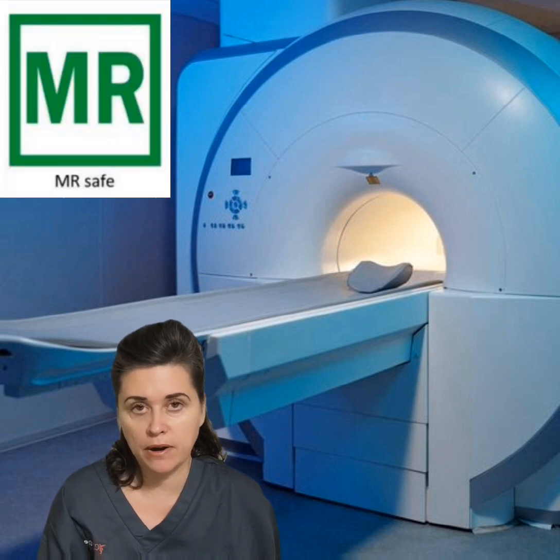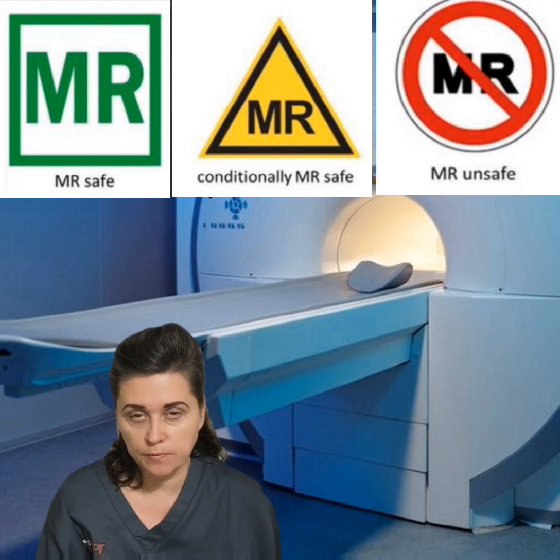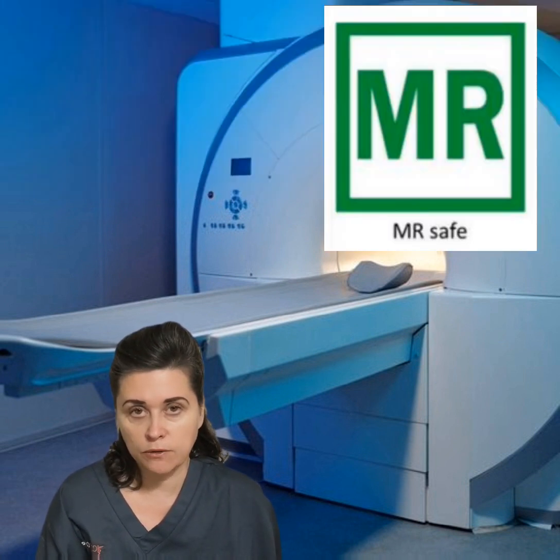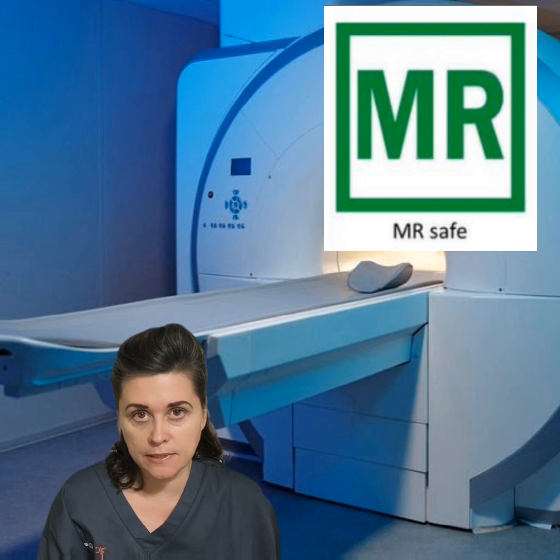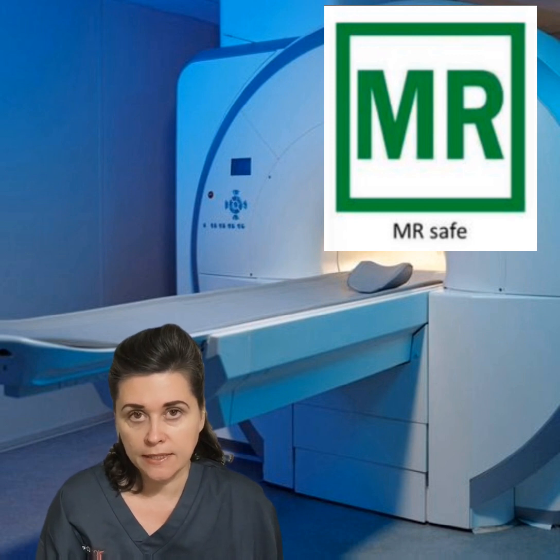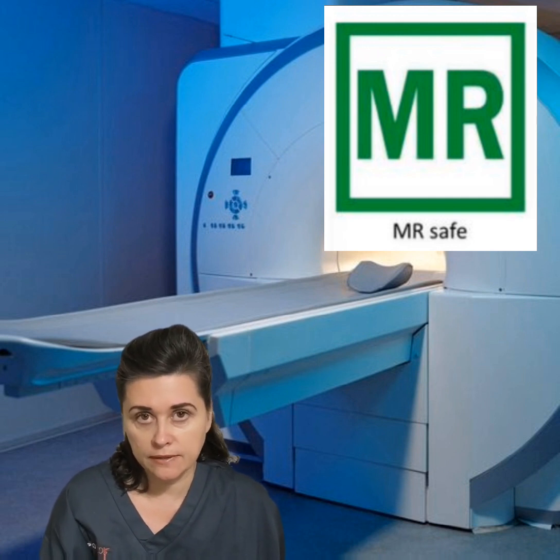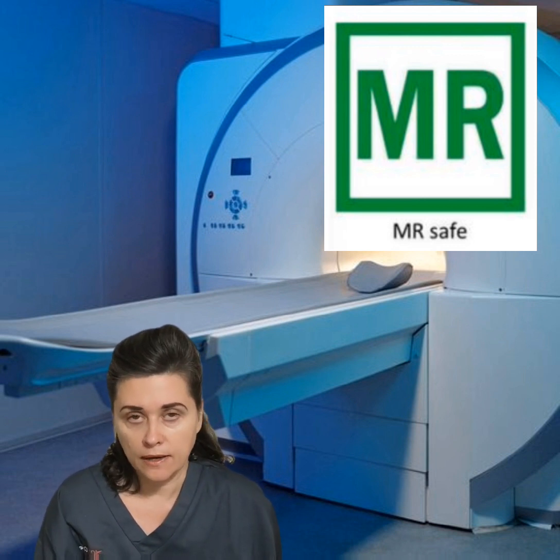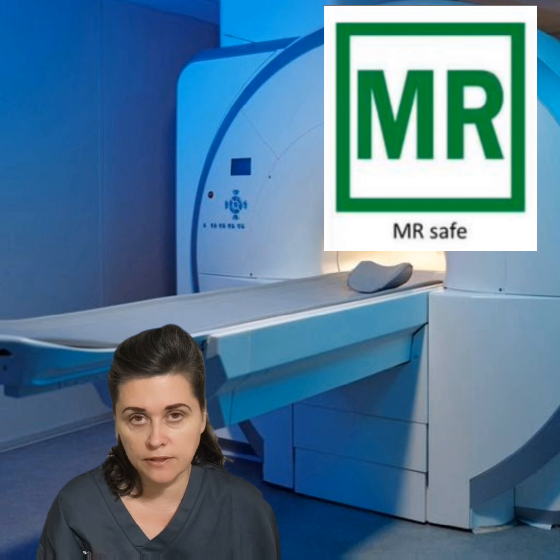In the MRI environment, it is crucial to know the difference between MR safe, MR conditional, and MR unsafe items. MR safe items are usually non-metallic and possess no or minimal heating potential. We have to remember that we have two major forces to watch out for in the MRI scan room. It is B0, which is the static magnetic field, and RF, radio frequencies, that tend to heat up things and objects. So MR safe items are labeled as green letters M and R on a white field and surrounded by a green square box.